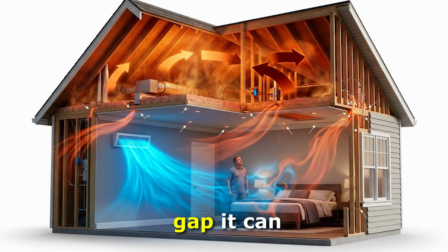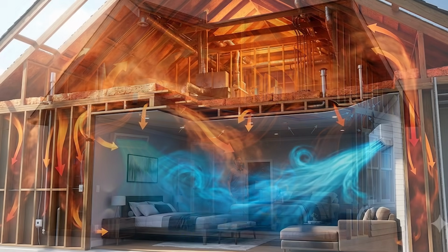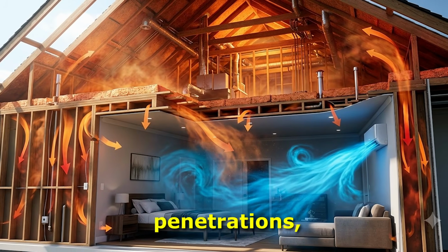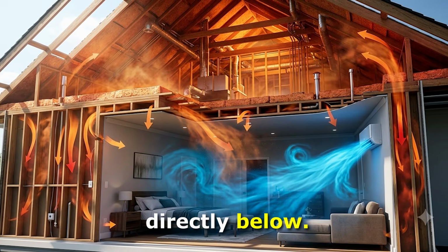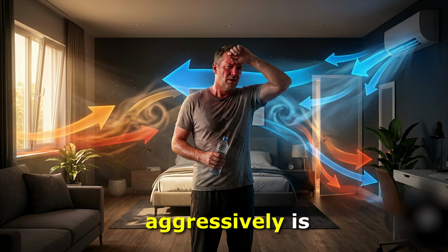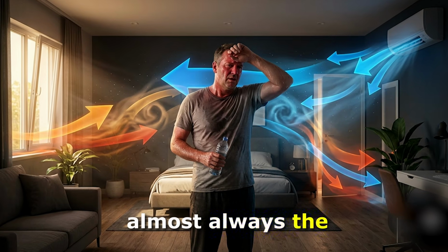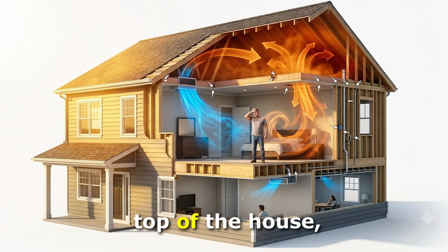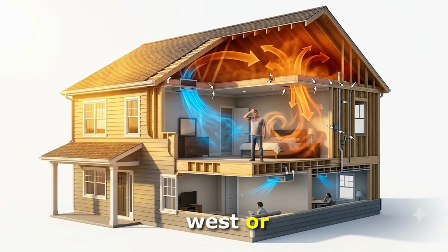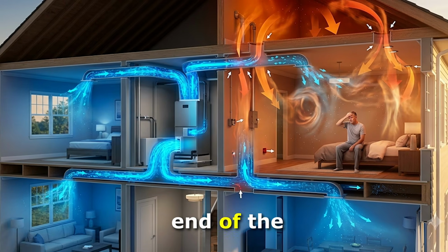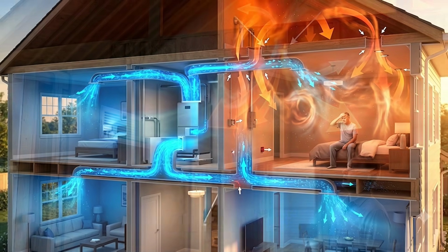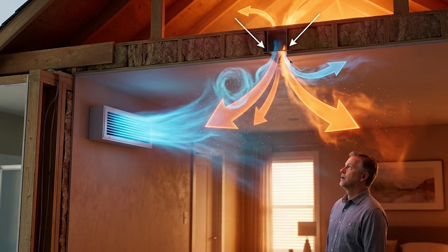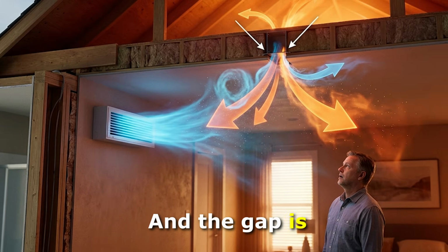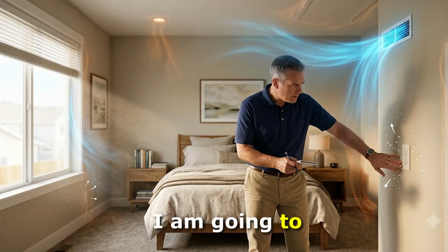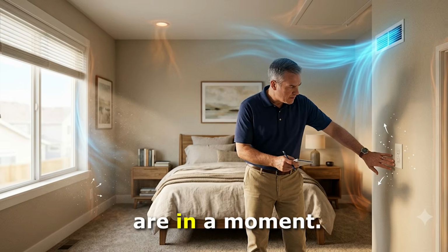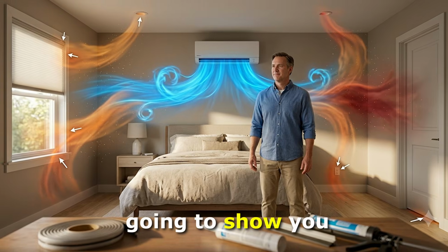It finds every gap it can, and it moves into wall cavities, down through ceiling penetrations, into the room directly below. And the room it moves into most aggressively is almost always the same room, the one at the top of the house, the one facing west or southwest, the one at the end of the duct run that already gets the least airflow. The hot room is not random, it is physics, and the gap is where the physics shows up. I am going to show you exactly where these gaps are in a moment, and then I am going to show you the fix.